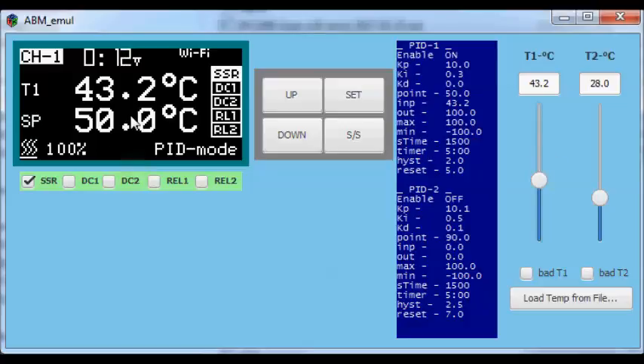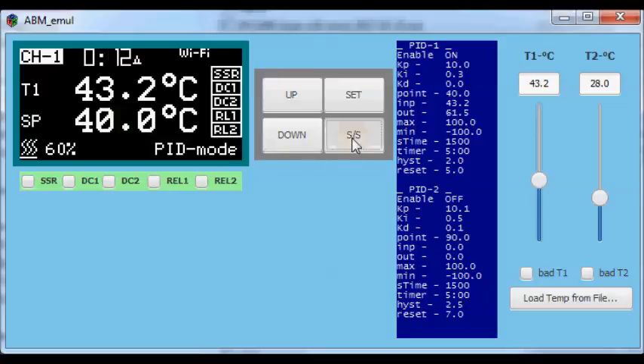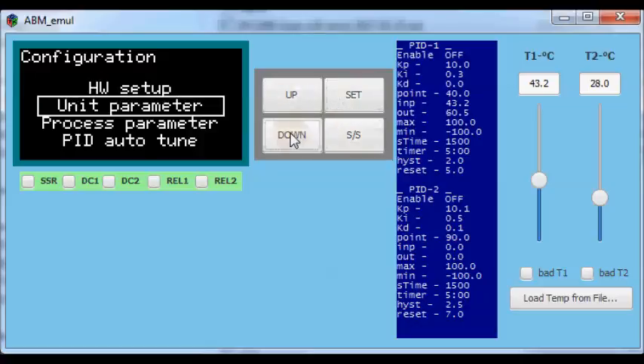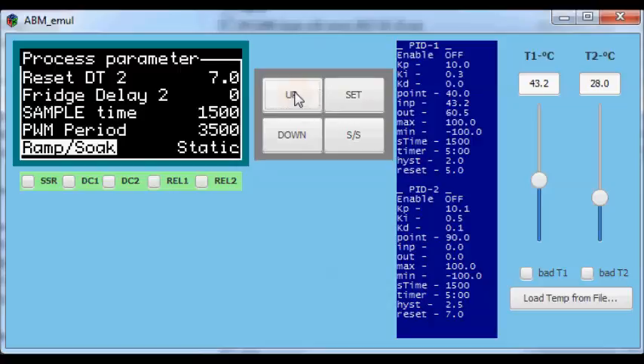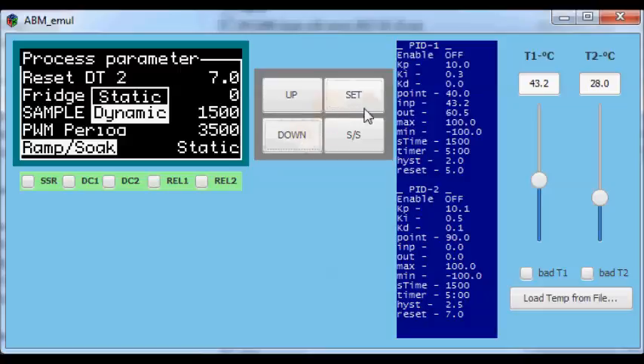Through the profile mechanism you can modify the setpoint with the speed and value you desire for your process. When the last step is reached, the temperature is kept stable. Back in the configuration, under process parameters, you can decide if the ramp soak is static — where the time flows independently from the temperature — or dynamic, where the soak time starts whenever the temperature reaches the setpoint.